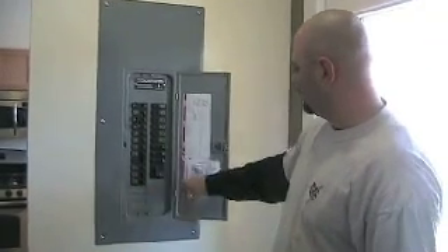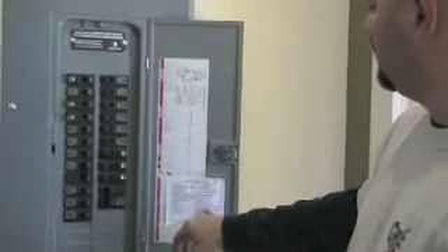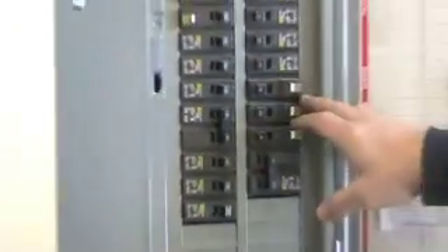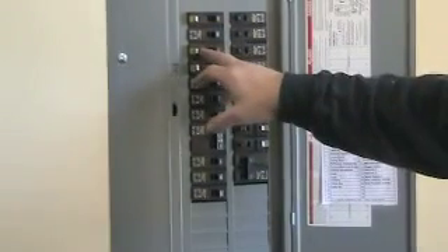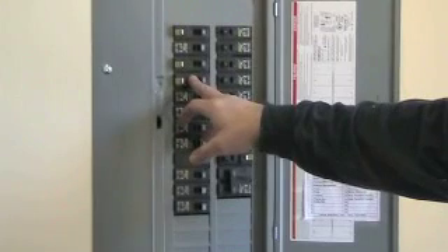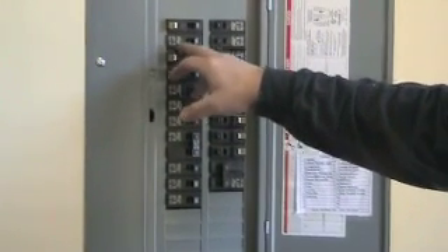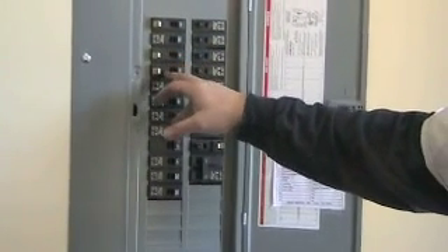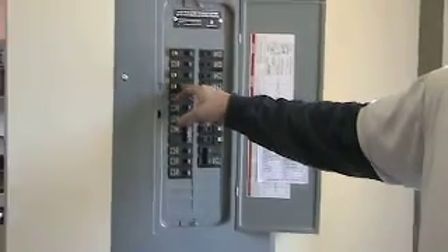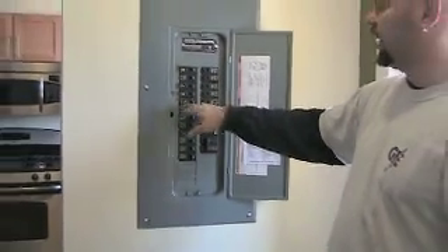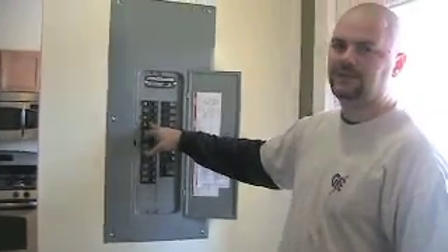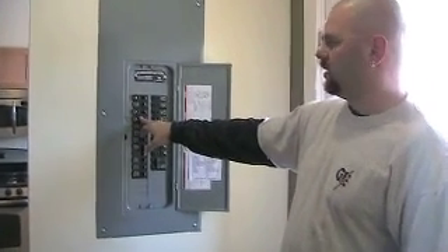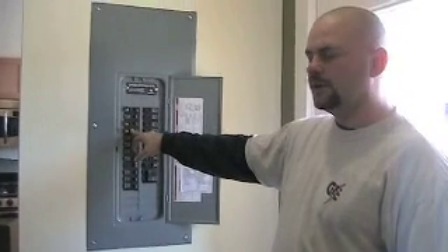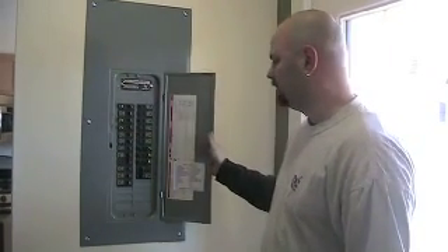Each breaker is labeled with the panel schedule here, and it corresponds to the breakers here. These are arc fault breakers, newly required by the 2008 code. So if you do have a problem with your bedroom, dining room, anything other than a mechanical device, you may want to check to see if your breaker has been tripped. That could be caused by an arc in an extension cord or anything to that effect.